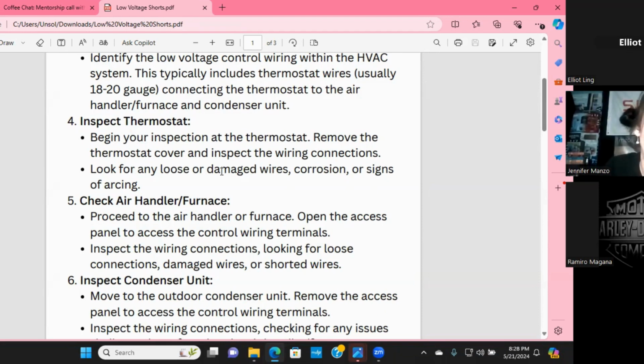So to do that, you begin your inspection at the thermostat, remove the thermostat cover and inspect the wiring connections. When I say inspect, I mean that you're looking for any loose wires. A lot of people, even technicians that have been around for a long time, don't correctly know how to implant or seat a wire into a thermostat correctly. This happens all the time. Make sure for yourself, because then you know that it's not a loose wire causing it. All you have to do is a little tug test on each wire. If it's tight, it's tight. If it's not, tighten it.